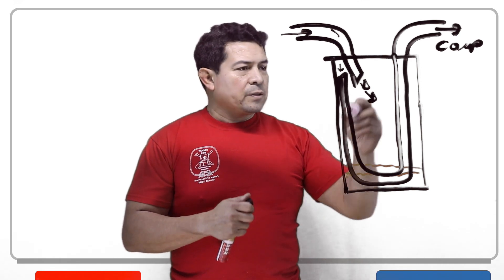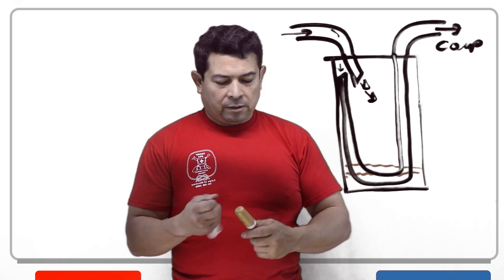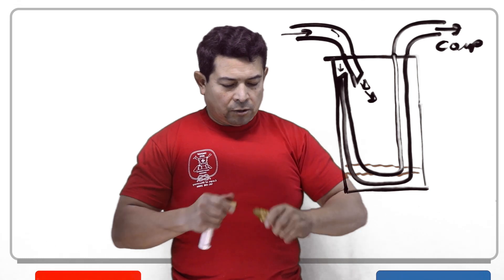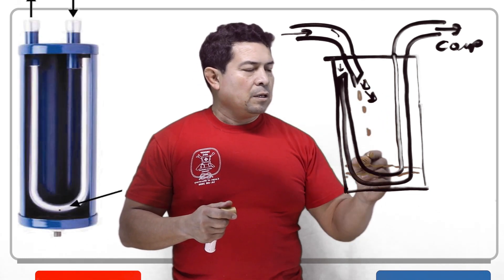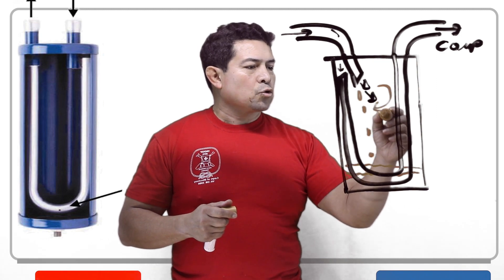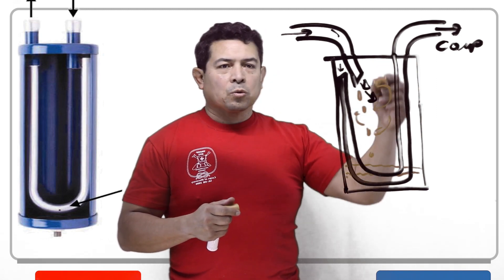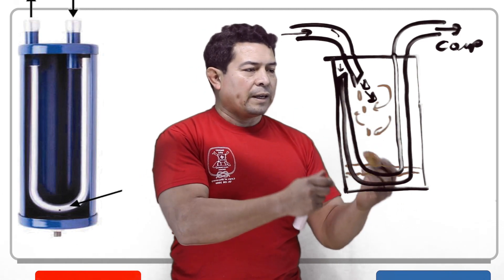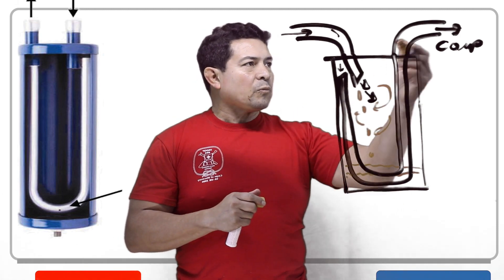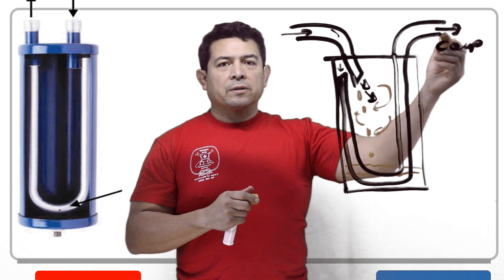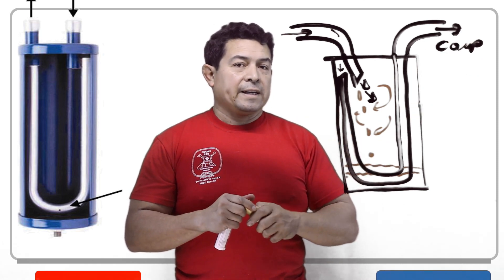So if there's any liquid refrigerant coming in, what's going to happen is it's going to get trapped — it's going to drip down and swirl around so all the droplets fall out. All of the oil that might be in here falls out and only refrigerant gas is going to be going back to the compressor.